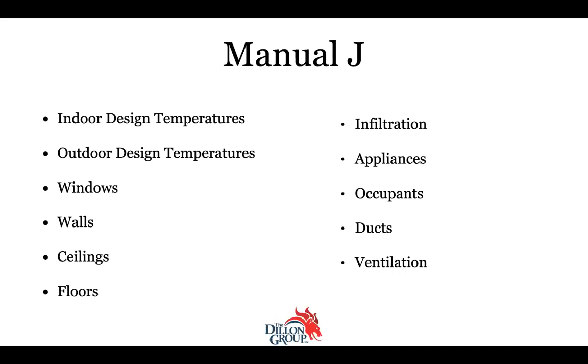So Manual J looks at the indoor design temperatures, the outdoor design temperatures, windows, surface areas, walls, surface areas, ceilings, surface areas, floors, surface areas. It looks at the infiltration, the appliance load, the occupants, the ducts, the ventilation. Manual J looks at all of these things based on the design of the house, the blueprints of the house, and the construction specifications, things like that.